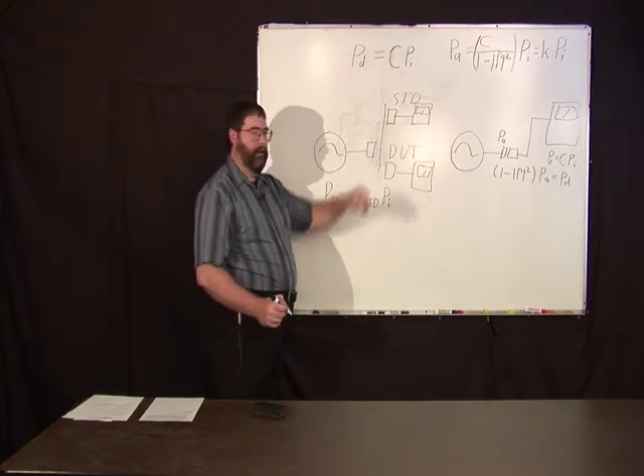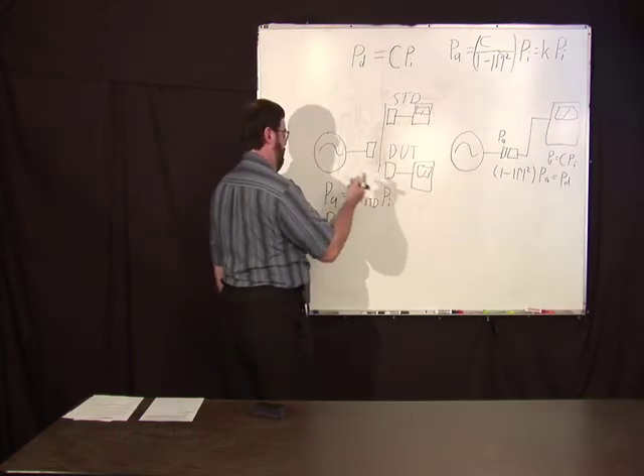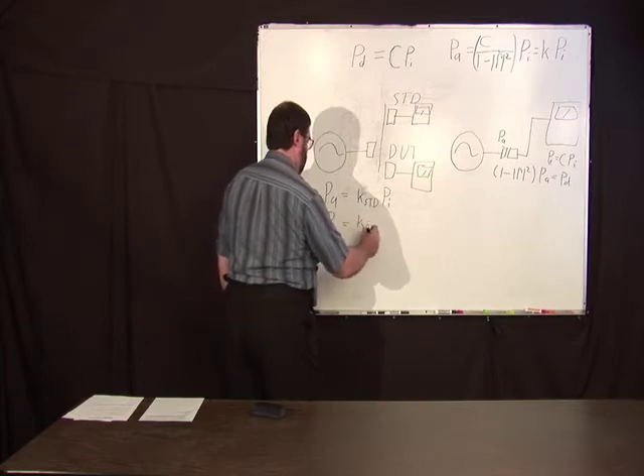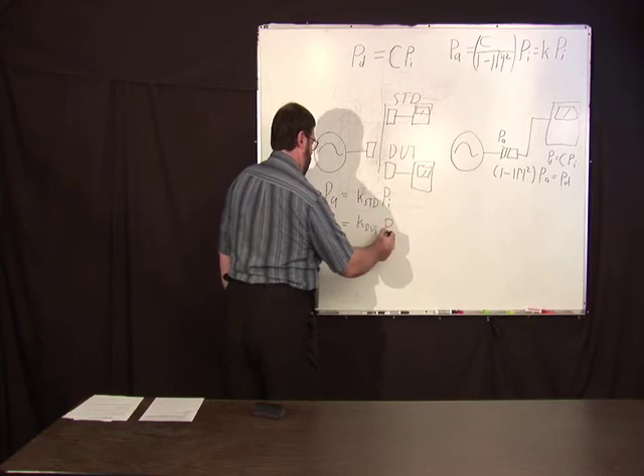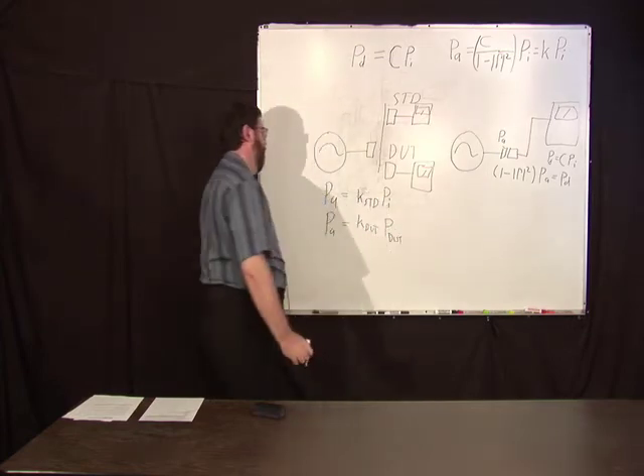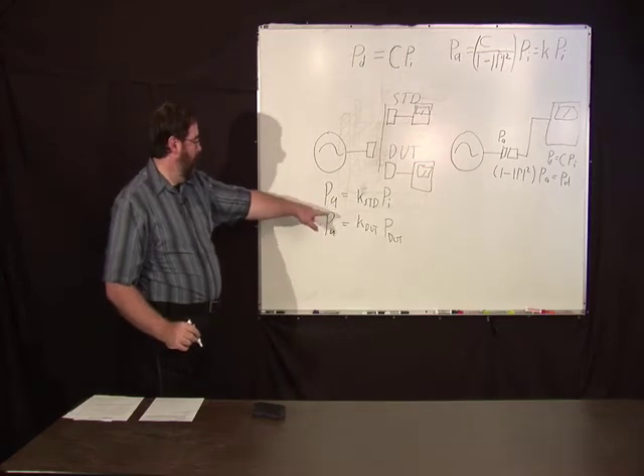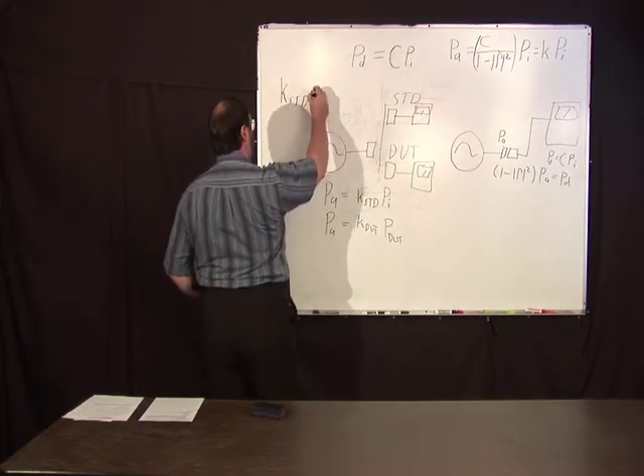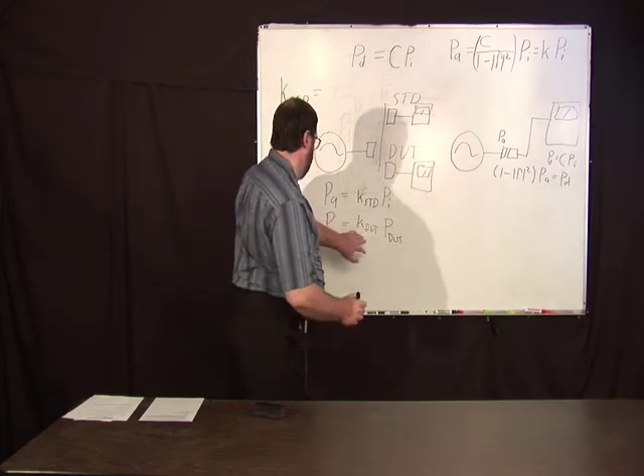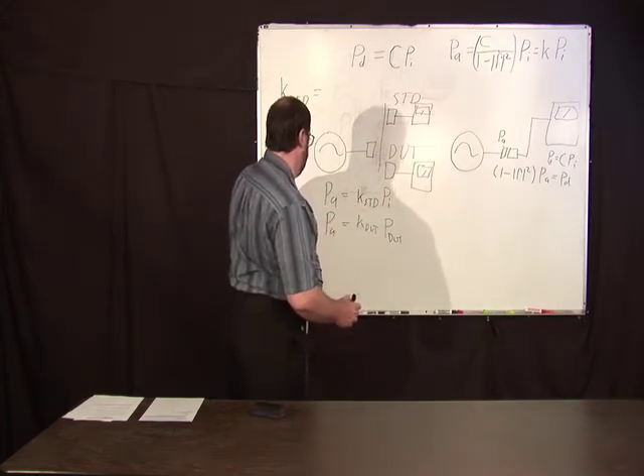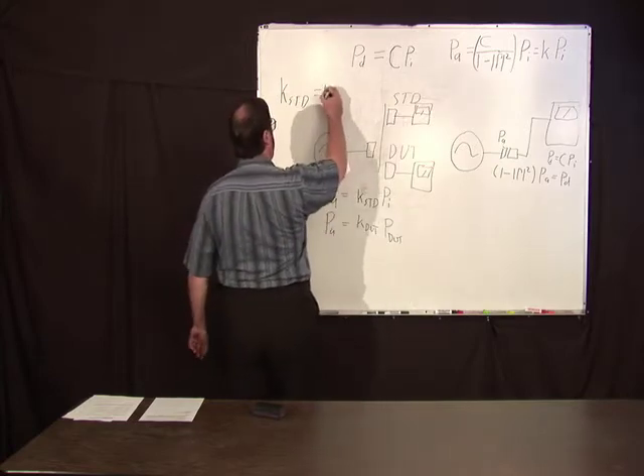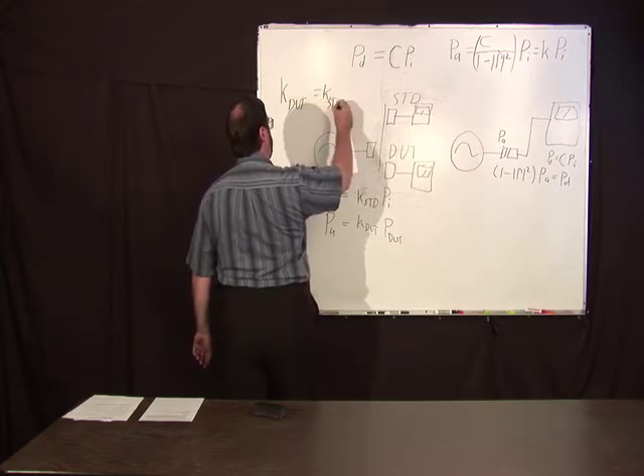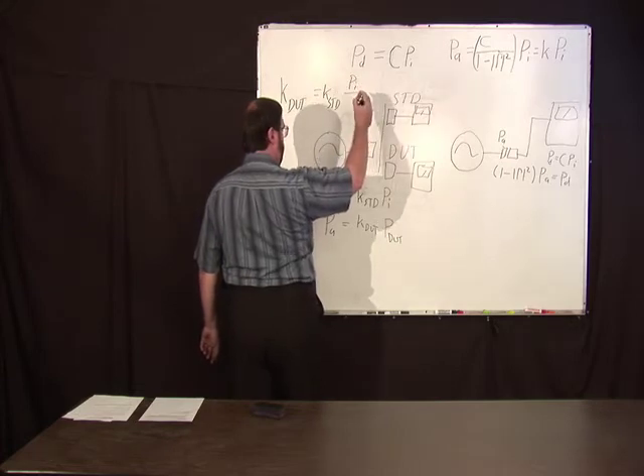Then we put the DUT on there and we measure the available power. We measure some power. It's going to be K sub DUT times P sub DUT. So we can solve between these two. We can solve for this. K sub DUT is K standard times P sub i over P sub DUT.